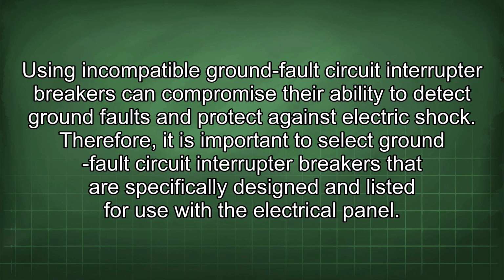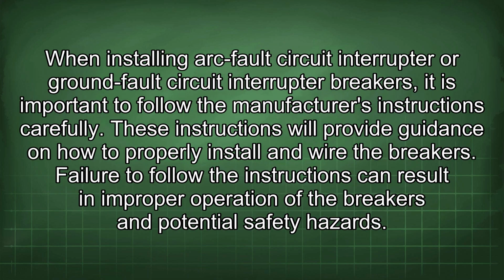Therefore, it is important to select ground fault circuit interrupter breakers that are specifically designed and listed for use with the electrical panel. When installing arc fault circuit interrupter or ground fault circuit interrupter breakers, it is important to follow the manufacturer's instructions carefully. These instructions will provide guidance on how to properly install and wire the breakers. Failure to follow the instructions can result in improper operation of the breakers and potential safety hazards.